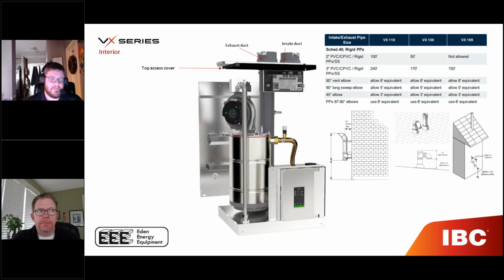You also have the ability to pull from room air, or if you're exhausting through the roof, you can pull your intake from the sidewall instead of running them both up that way. That said, we also have an inline fresh air intake filter kit. That's really useful if you're in an area where you're worried about the fresh air coming into your boiler being potentially contaminated. I deal a lot with rural properties near dirt roads or farming fields, and even in the city some areas can be pretty bad. It's definitely worth having a look, and that's an optional add-on you can talk to Mike about later.